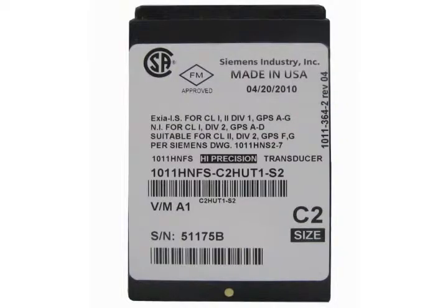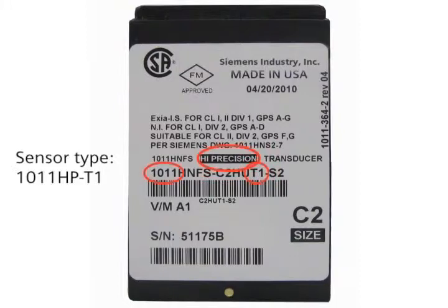Now we will enter the sensor data into the SITRANS FUS1010. This will help us mount the sensors for optimal performance. The data we need is the sensor type and size. This data is on the sensor label. Since the sensors are supplied as a matched pair, we should also verify that they have the same serial number followed by an A or B.